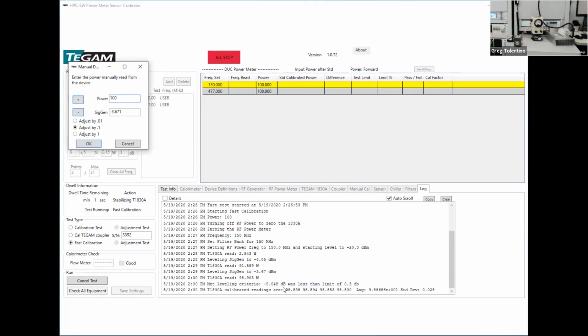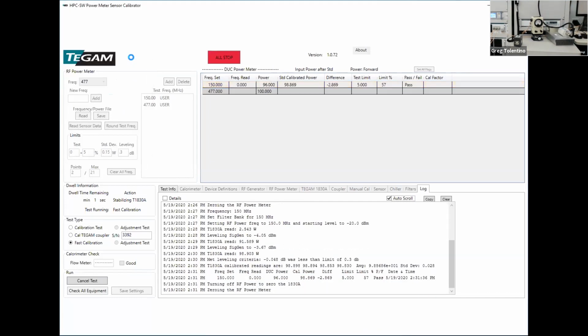There it is. Is that box displaying on the shared? Okay, great. All right, so I could use these controls to raise and lower the generator by a dB, a tenth of a dB, or a hundredth of a dB to get the needle perfectly aligned with the scale to reduce uncertainty. In this case, I'm just going to read the number off the scale and type it in. Okay, I read about 96 watts. So I'll type 96 in, hit return. It says that the 1830A in the coupler, we're indicating almost 99 watts, so we're off by 3 watts or so, which is 57% of the test limit, so the unit passes.